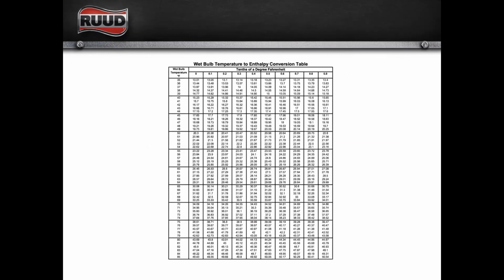So this is the static pressure. I mean, sorry, not the static pressure. This is the wet bulb temperature to enthalpy conversion table. So when we're talking about wet bulb temperature, we're talking about how much heat is in a sample of air, right? And we're going to take that wet bulb temperature, and there is a direct correlation between wet bulb temperature and enthalpy.